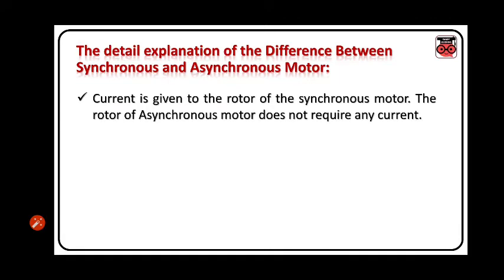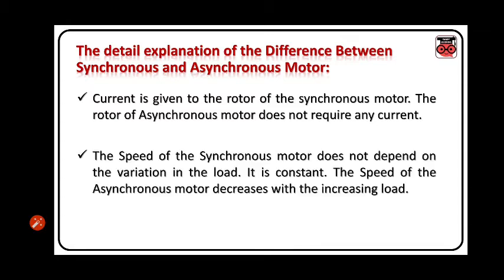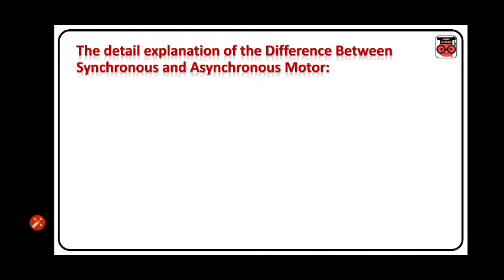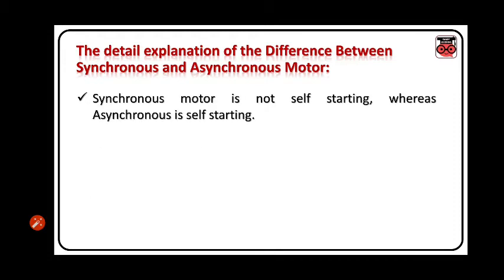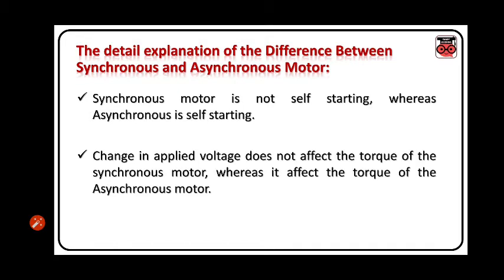Current is given to the rotor of the synchronous motor, while the rotor of the asynchronous motor does not require any current. The speed of synchronous motor does not depend on variation in load — it is constant. The speed of asynchronous motor decreases with increase in load. Synchronous motor is not self-starting, whereas asynchronous motor is self-starting. Change in applied voltage does not affect the torque of the synchronous motor, whereas it does affect the torque of the asynchronous motor.